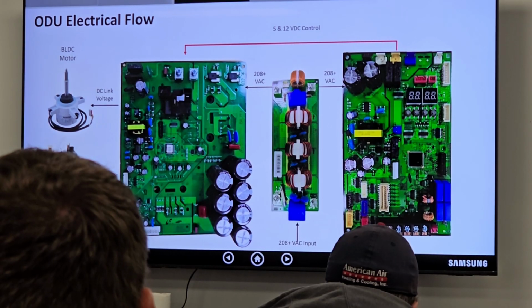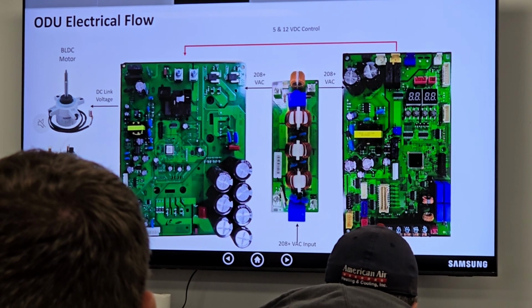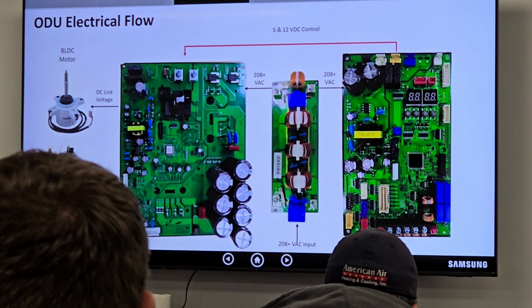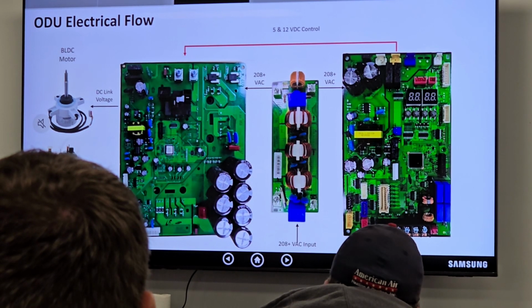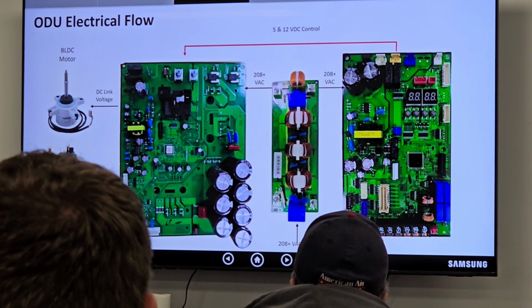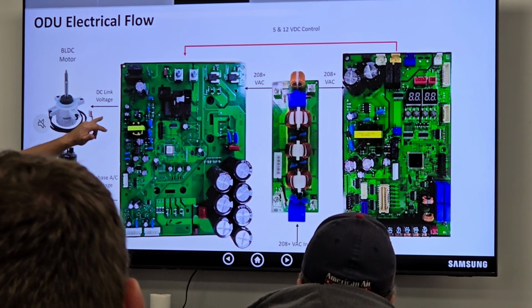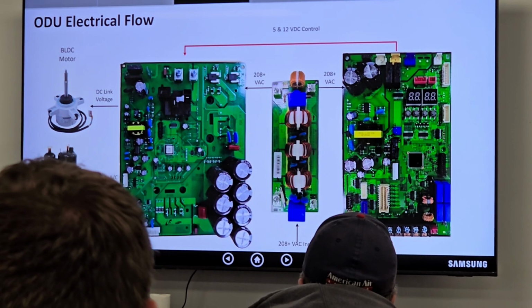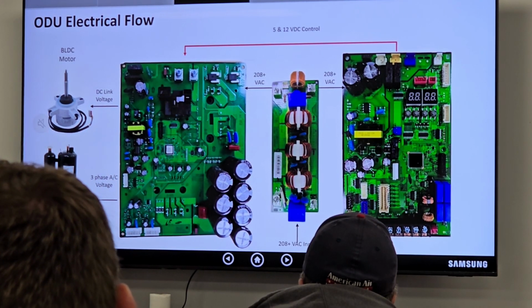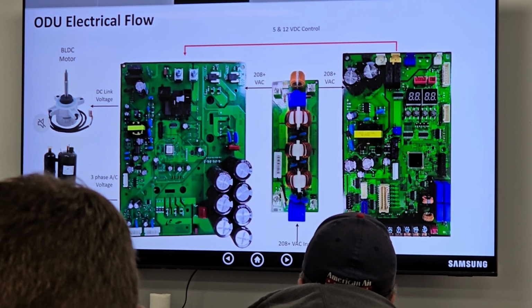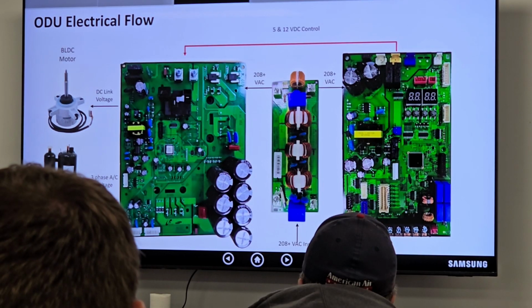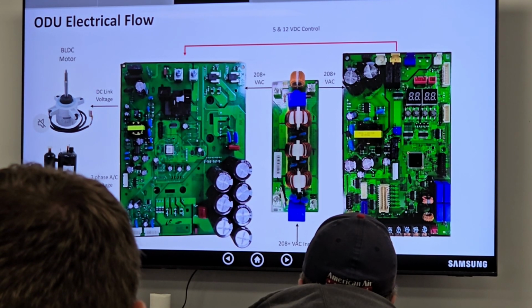How do I know what my DC current should be? If I know what my incoming voltage is, and I multiply it times 1.4, I know what my DC link voltage should be. So if I've got a problem and we need to know if the inverter is producing voltage, I can actually go to the fan motor and check for DC link voltage as well, and it should be roughly 200, whatever my incoming voltage times 1.4 is. So I know my board is producing the power.